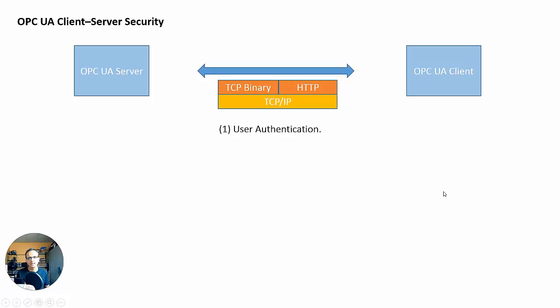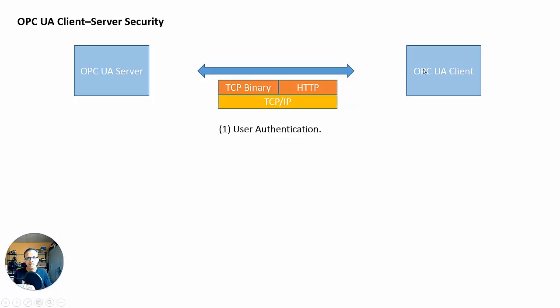The first one is called user authentication — a really big phrase for something that means username and password. You use it every day: username and password to log on to your laptop, your desktop, your phone or whatever. So essentially, the UA server will have within it the ability for you to configure users. Every user will have a username and password, so when the client is connecting, you have to put that username and password in the client and then say connect. You as the designer, engineer, or technician have to do that.